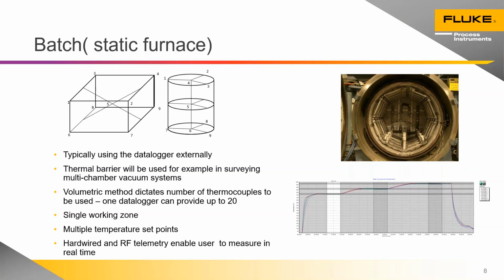For a cylindrical work zone, the sensors are placed at 120-degree intervals around the circumference at the top, middle, and bottom. And then another 3 sensors are placed on the center axes. Now, the topic of the number of sensors used is quite a complex one. It's not something we can get to in much more detail here, but suffice to say, in a static furnace, the number of sensors to be used depends on the furnace class and the working volume. So as volumes get larger, the number of thermocouples will become greater. And table 11 within AMS 2750 is the reference document for that.